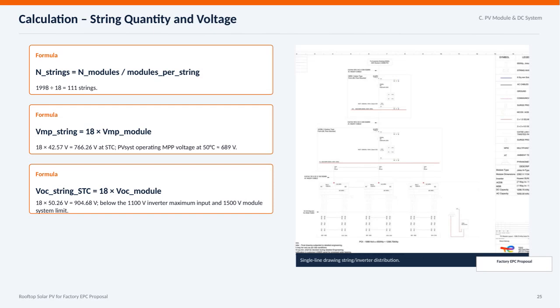Here we're calculating the string quantity and voltage for the rooftop solar PV system in our factory EPC proposal. Starting with the number of strings, we divide the total number of modules, 1998, by the number of modules per string, which is 18, resulting in 111 strings. For the voltage at maximum power point, or VMP, we multiply the 18 modules by the VMP of a single module, 42.57 volts, giving us 766.26 volts at standard test conditions. However, considering operating conditions at 50 degrees Celsius, the voltage is approximately 689 volts.